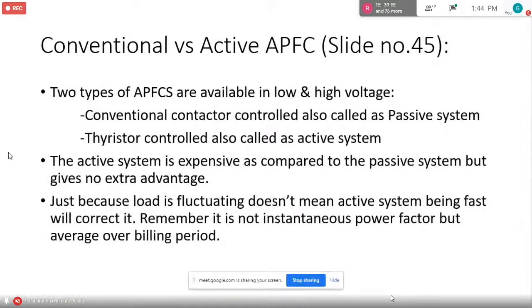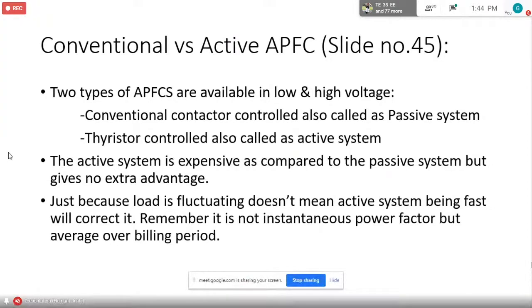Conventional versus active power factor correction system. Two types of power factor correction systems are available in low and high voltage. Conventional contactor controlled, also called a passive system. Thyristor controlled, also called an active system. The active system is expensive compared to the passive system, but gives no extra advantage.